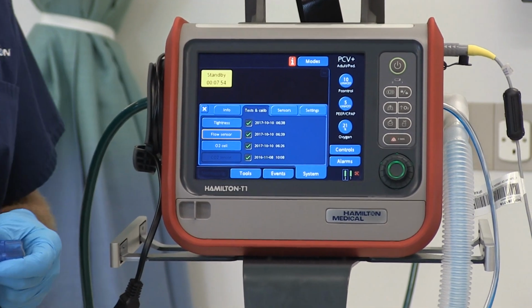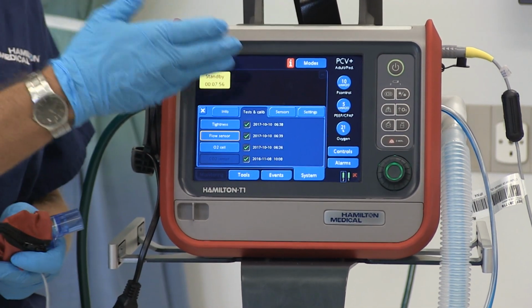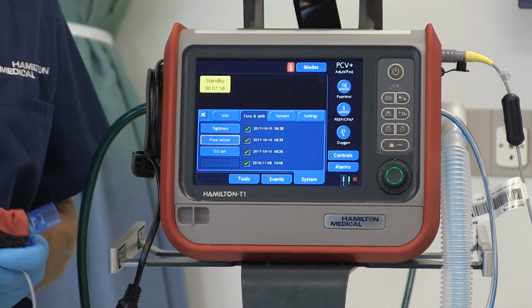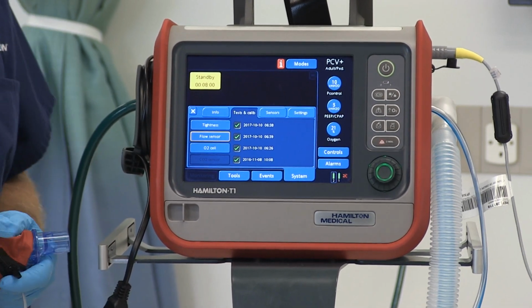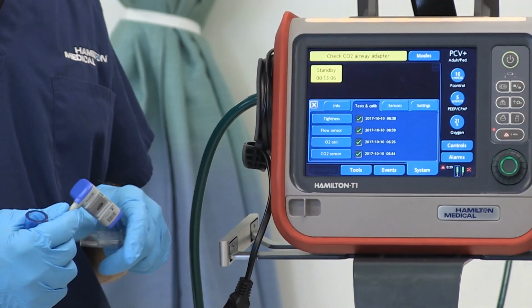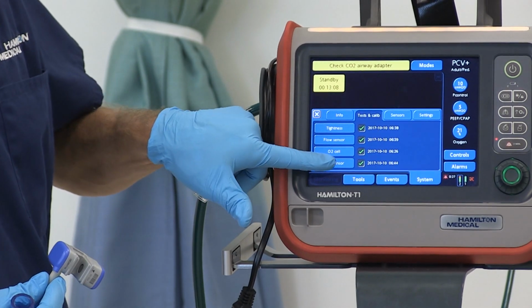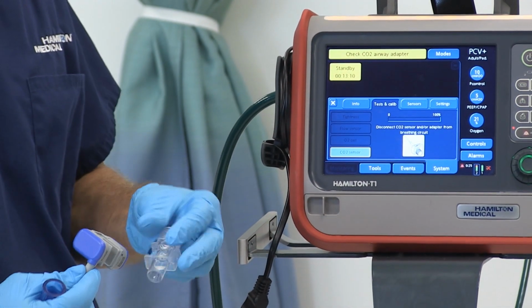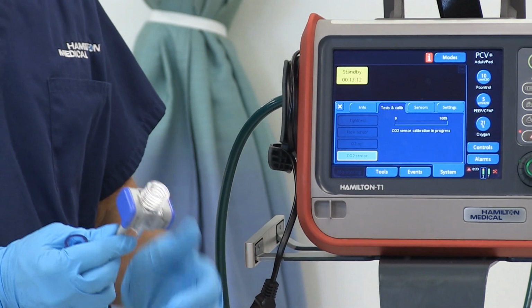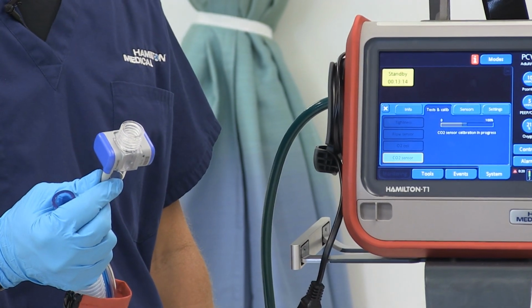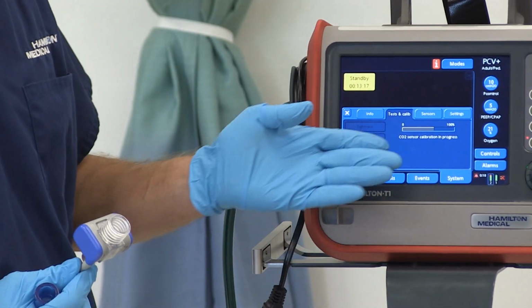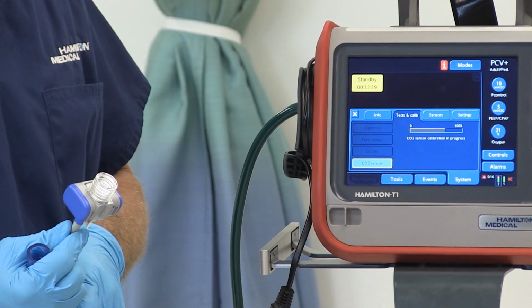The next test is called O2 cell. We don't need to do that unless the ventilator gives us a message up here in the message bar that we need to calibrate the O2 cell. So now let's perform the end-tidal CO2 sensor calibration. Press here on the screen, attach your cuvette. The test must be performed on room air. And again, I'm going to pay attention to the screen.